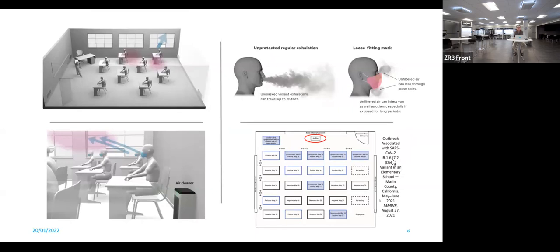If I can't upgrade my HVAC system, supplement it with HEPA filtration. Okay, I bought a HEPA filtered air filter, I'm good to go. Unfortunately, that's not the case, because it's not just about HEPA. It's about airflow dynamics, proper dilution, and proper ventilation effectiveness in room mixing. If you don't have all three of those things, it's really an equation that needs to be done delicately. If you don't have them, then you don't have the proper solution.